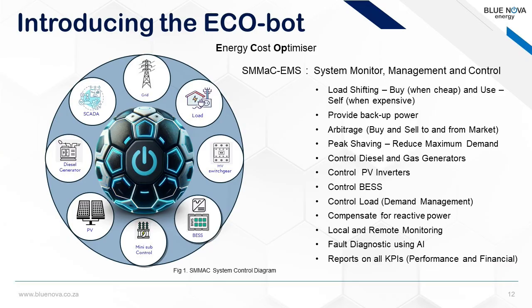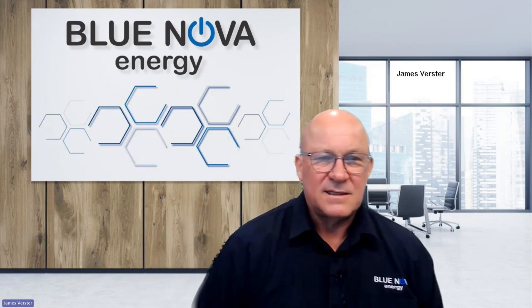and then once the grid falls away, it forms its own island and generates its own power with its own reference, controlling the loads, having to control medium voltage switchgear, having to control the battery energy storage system, charging and discharging, optimizing that. Normally on these sites, one would have a whole network of mini subs, which needs to be controlled in the case of a blackout and a black start. There will be PV that would be needed to be controlled, especially if you don't want to export the PV, or you do want to export it and you have to regulate it or throttle it down in an off-grid scenario when the batteries are already full. Controlling diesel generators and maybe gas generators, and also integrating to the SCADA system on some of the existing sites.